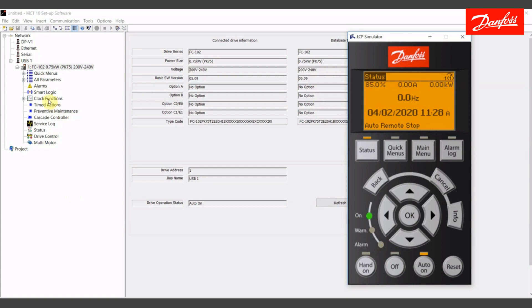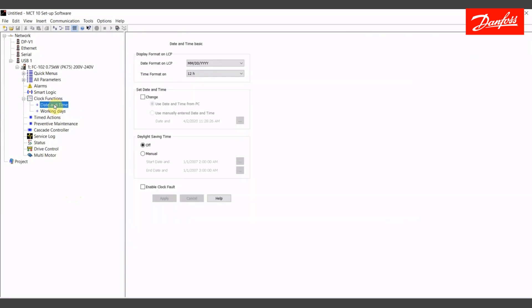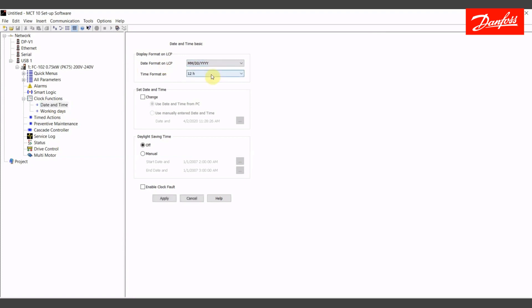First, I'm going to move into the clock functions wizard. The clock functions wizard is going to let us set the date and time automatically with my PC. If you are connected on the network side, the live drive, you'll have this tab here for date and time. If you're working on the project side, you'll only see this working days tab. It'll allow you to set up the date and time automatically with your PC. Use this button that says set time and date, apply that, and it will use your PC to write the clock.